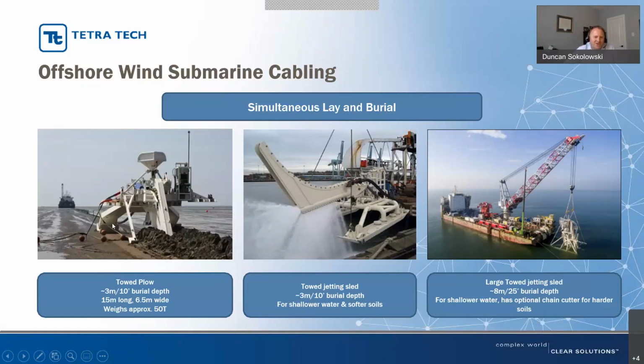The plow gets towed along; the cable here is laying on the mud. If it's in deep water, it won't do this - it just hangs in the water column. It goes in through the plow; you can see it come down through the plowshare, and it gets injected, if you will, down into the seabed in one simultaneous operation. Normally with standard plows you can get to about 3 meters, or 10 feet, of burial, and the machines themselves are roughly 15 meters, about 50 feet long, weighing about 50 tons.